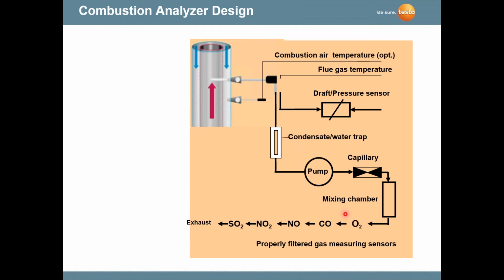If something happens to be disconnected, or if there's a crack in the water trap, or if the particulate trap cover is not tightened, and we get excess air coming in here, we're diluting our flue gases. Remember, our flue gases in here are 3, 4, 5, 7% oxygen, and hopefully very little carbon monoxide. If air comes in through our hose assembly somehow, then we're bringing in that fresh air at 21%. We're diluting our oxygen, therefore creating not a very accurate efficiency rating. So I'm really just saying, maintain your probe and hose assembly, make sure there's no cracks in it, no leaks, anything like that.